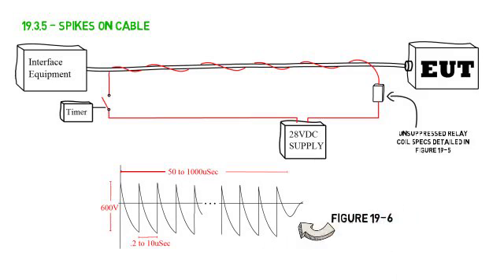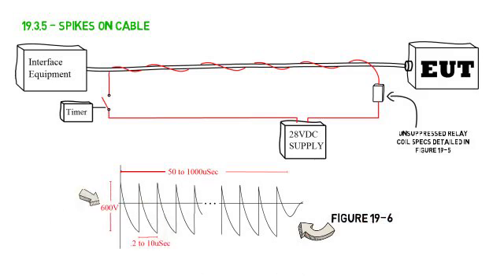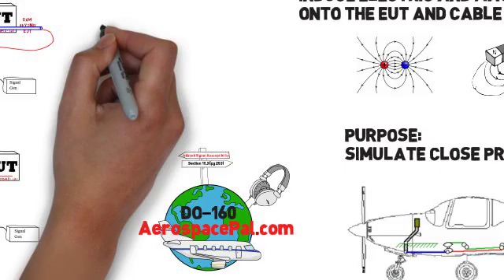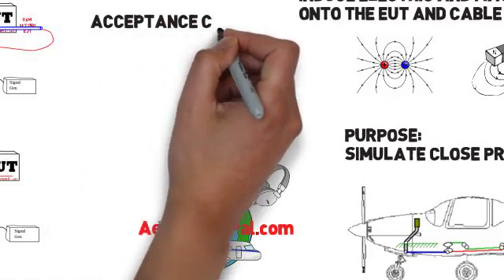The waveforms achieved will not be perfect. In figure 19-6, the note recognizes that some spikes will be less than 600 volts peak-to-peak. Aim for at least 75% of the spikes being above 600 volts peak-to-peak.